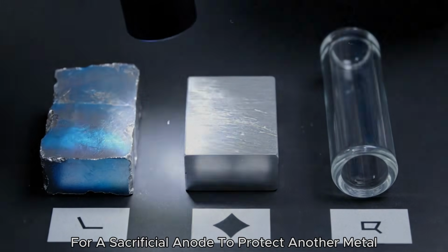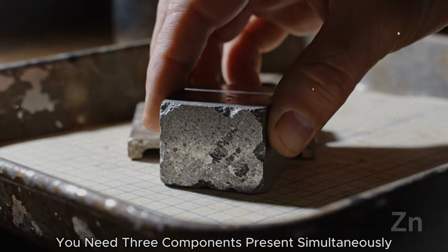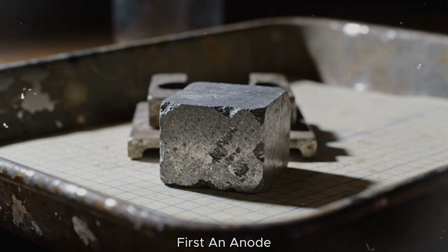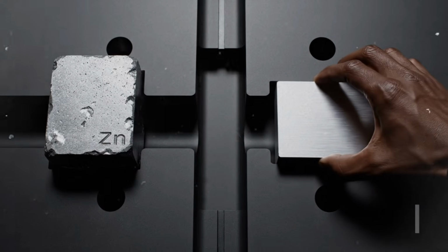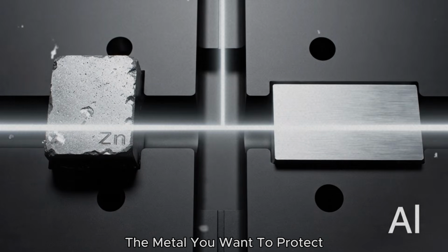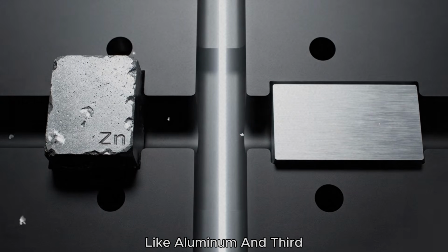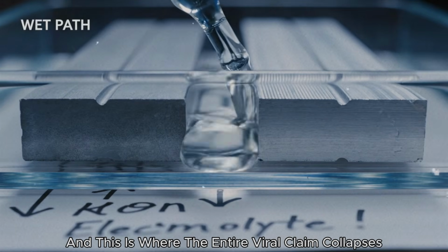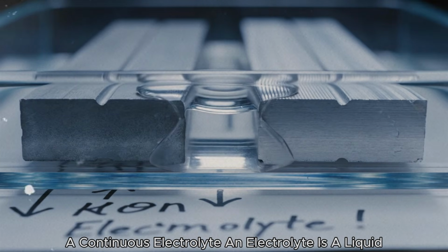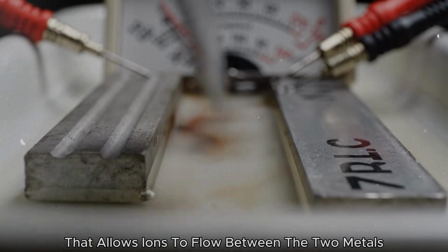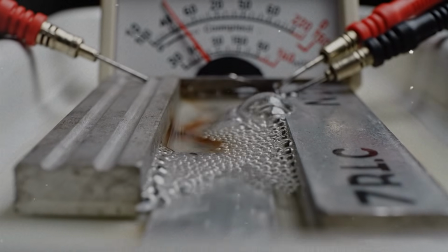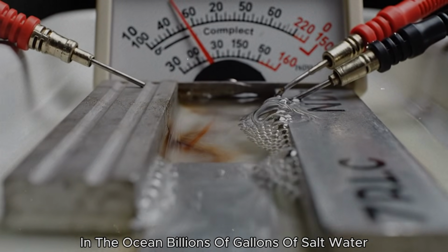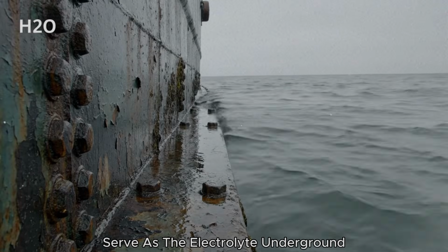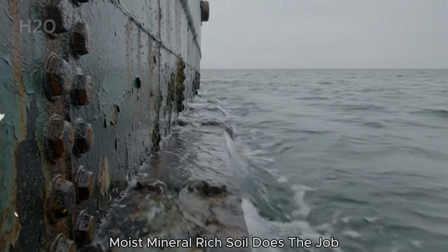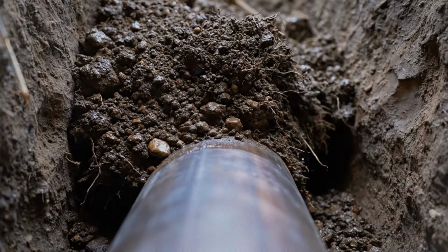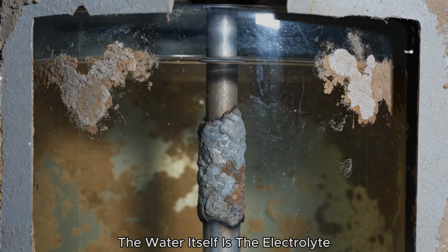For a sacrificial anode to protect another metal, you need three components present simultaneously. First, an anode, the sacrificial metal like zinc. Second, a cathode, the metal you want to protect, like aluminum. And third, and this is where the entire viral claim collapses, a continuous electrolyte. An electrolyte is a liquid or wet medium that allows ions to flow between the two metals, completing the electrochemical circuit. In the ocean, billions of gallons of salt water serve as the electrolyte. Underground, moist, mineral-rich soil does the job. Inside your water heater, the water itself is the electrolyte.